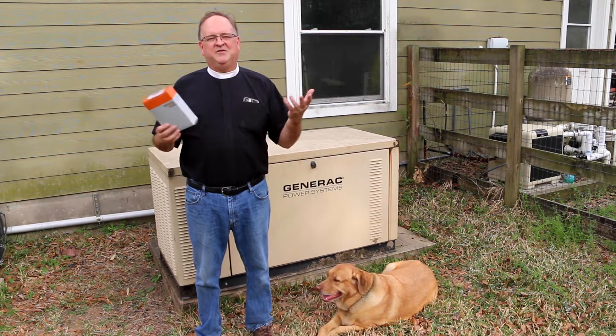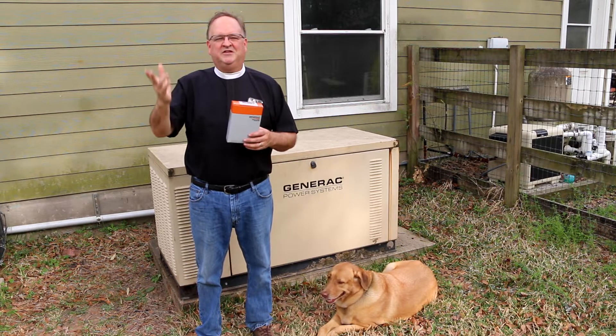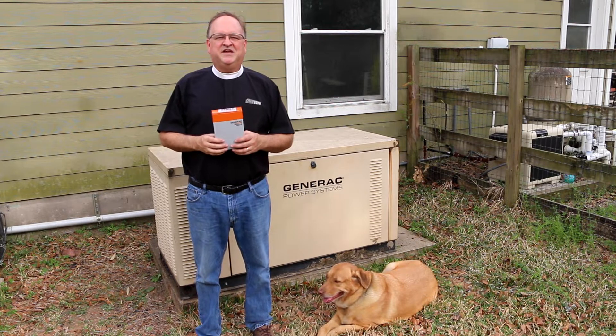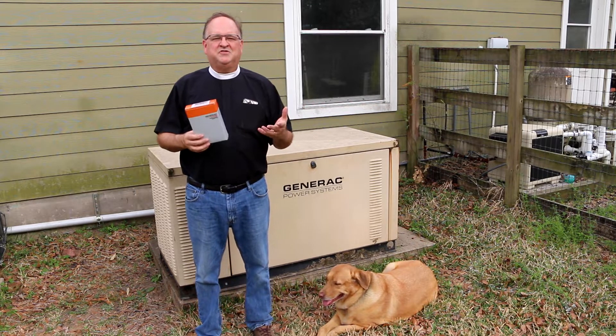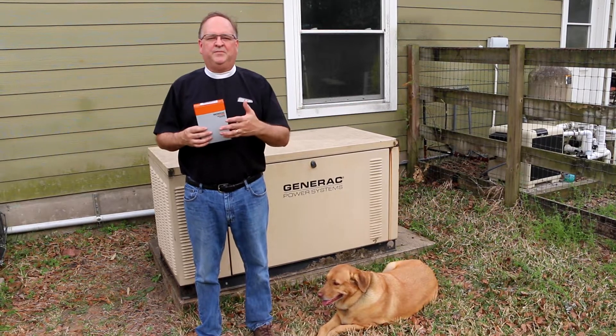We've had this generator since 2008. It has served us well over the last 13 years, and most recently through winter storm Uri and the prolonged power outages we endured here in southeast Texas. A couple of years ago, though, the generator shut down during its weekly exercise soon after starting, and the status lights indicated a low coolant level or high coolant temperature.